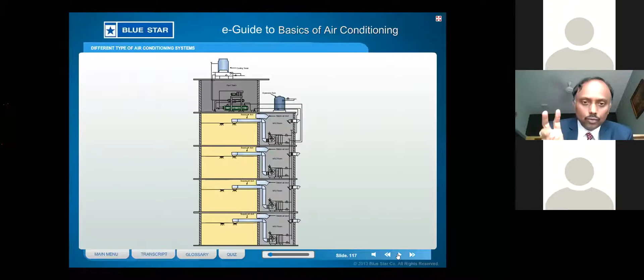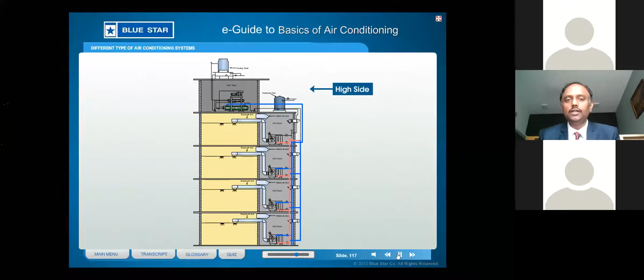So when you design such large projects, my request is that it is important you take inputs from any of the HVAC companies, any of the HVAC engineers. They will help you take care of the plant room dimensions and plant room spaces, what you need to consider. When you do this in the planning stage itself, it is very important that you design the AHU rooms and the plant rooms properly. You need to design the shafts, which will take care of the chilled water piping, electrical cabling and conduits. The shaft sizes you design in the building should take care of all this. Other than the HVAC part, you will also have electrical cabling running and firefighting piping coming. So please ensure you take care of that when you design the buildings.